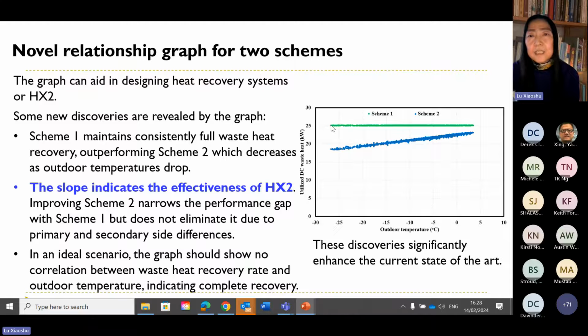First, Scheme 1 keeps constant, complete waste heat recovery, outperforming Scheme 2. Scheme 2 is this blue line. In Scheme 2, the waste heat recovery decreases as outdoor temperature drops. Second, this is very interesting, because we discovered that the slope of the line actually represents the effectiveness of the heat exchanger, with the optimal slope being 0 degrees, as the horizontal line of Scheme 1.